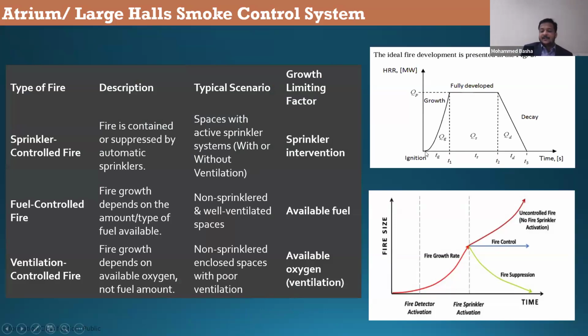What happens initially? The fire starts, the material starts burning, which is the ignition, we call it the growing stage. The fire grows. You can see TG. TG is the growth time. The growth time varies with the type of fire. If it's a slow fire, as I showed in the previous slide, it takes 600 seconds to reach 1000 kilowatts. The 1000 kilowatts is just a number they are showing. It can increase based on the materials burning. For a fast growth fire, the growth to 1000 kilowatts will take 150 seconds. So this is the growing time, which is called TG.